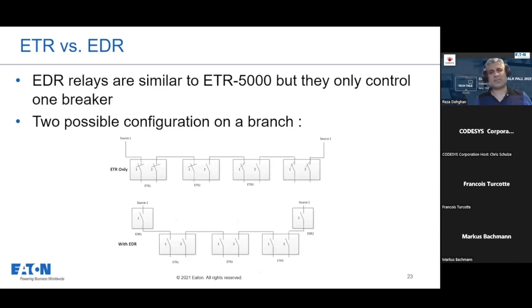Yeah, this one is not really important. It's just to say that when we're doing the configuration, we consider it for two main types of relays. For now, we are just going to use ETR, but they are working on another relay, which is called EDR 5000. The only difference is the EDR can control only one breaker. In the future, there's a possibility to use the second configuration, the bottom configuration. Basically, for the connection to the sources, they will use those EDR relays instead of ETR relays.